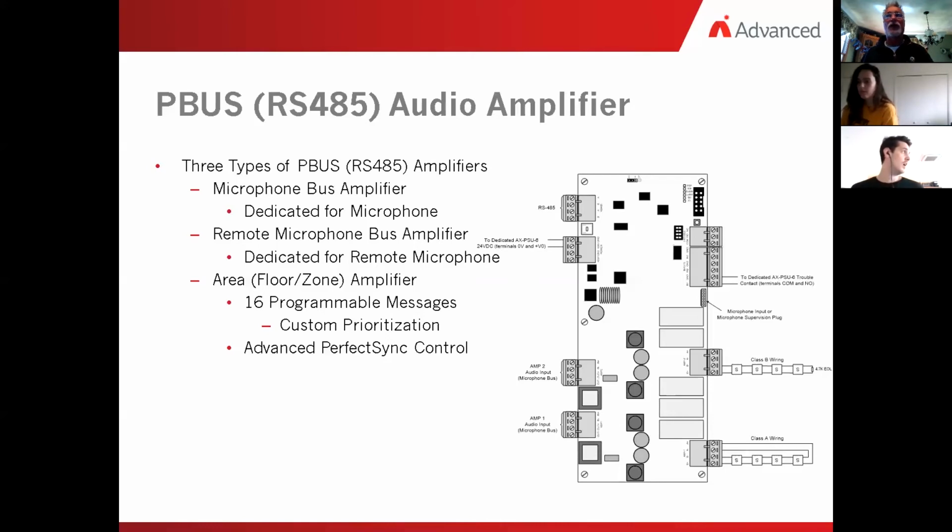One of the things that we do with this type of amplifier is that we use the perfect sync control across the P-bus network as well as the RS-485 network from panel to panel. In doing so, we synchronize the timing of all of the amplifiers, whether it's on a PEN or on a panel and across the network. So if we use a common message set for all of our amplifiers, they will in fact sound as if they are making a noise as a bulk system, one location starting the noise. They all sound like they're sounding together, and they do that via that perfect sync control.